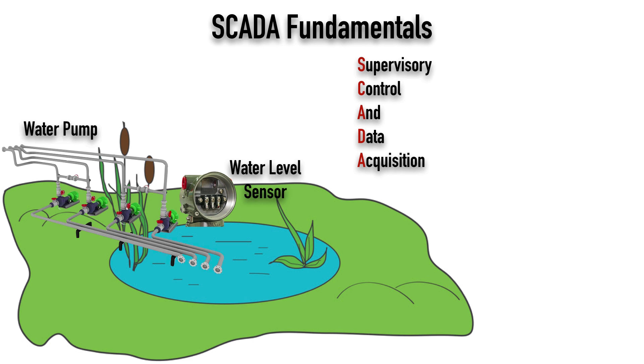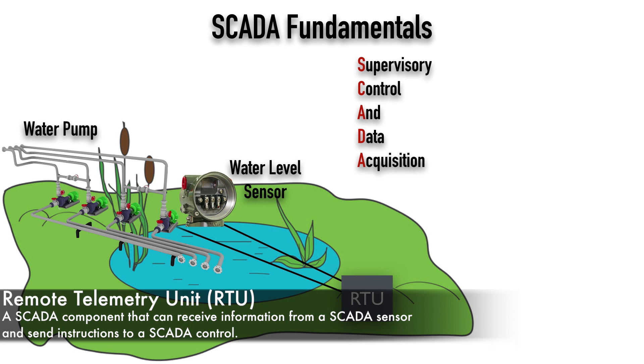SCADA needs another component to receive information from the sensor and, when instructed to do so, send a signal out to the control. In this example, we need something to tell the water pump to kick on. That SCADA component is called an RTU — a remote telemetry unit. It can receive information from the sensor and, when instructed to do so, it can send a signal out to the water pump to turn it on.